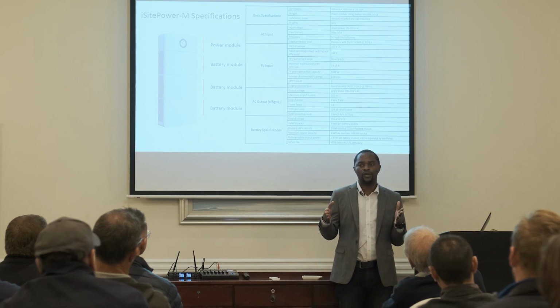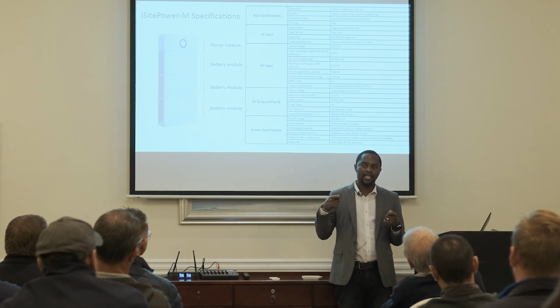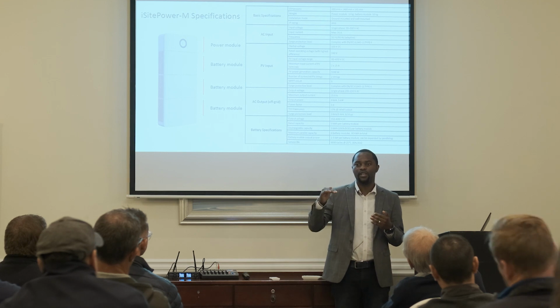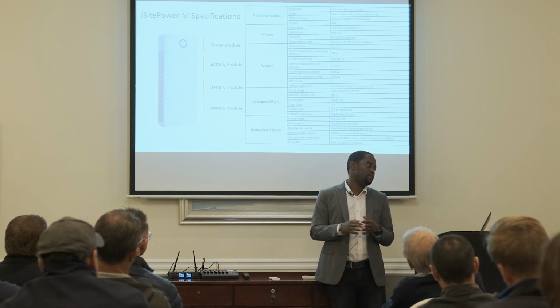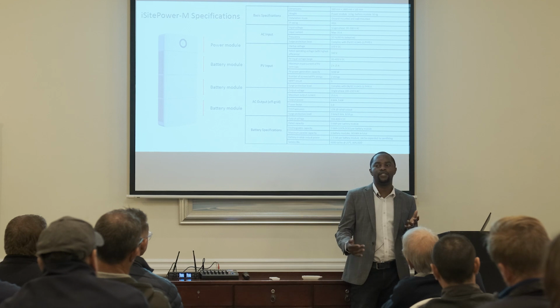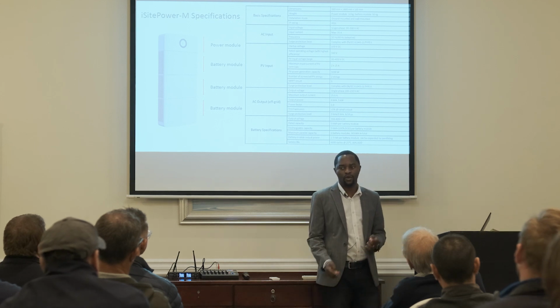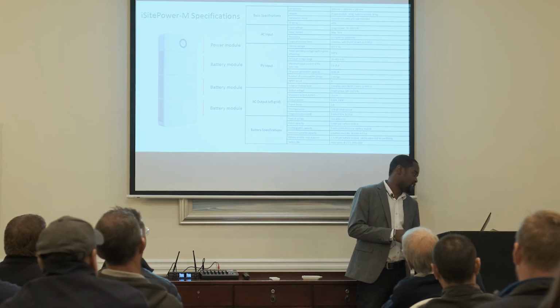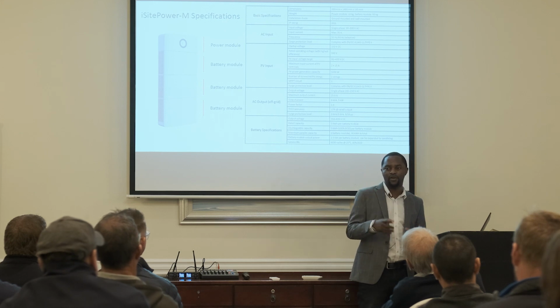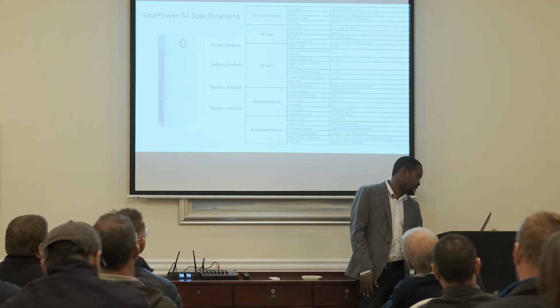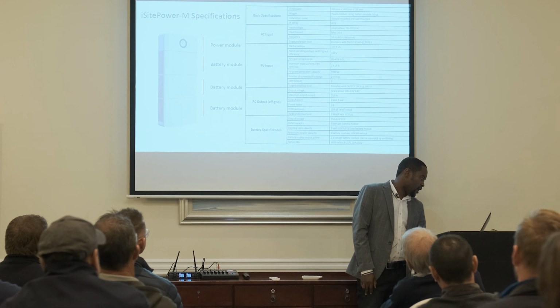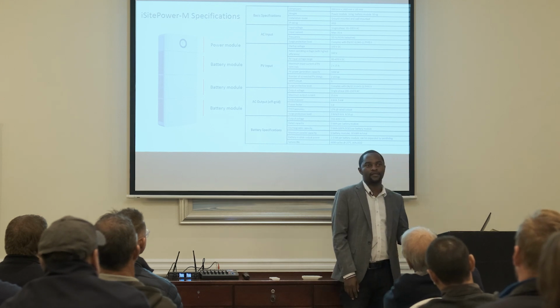But now let's say you've got 2 panels. The moment they start operating, the voltage drops below 100, but the MPPT will still continue working unless it drops below 90 volts. So the operating range is from 90, but the startup is from 100, to cater for at least a 10 volt voltage drop, and then you'll still be fine. Then you can have up to 5,000 watts.